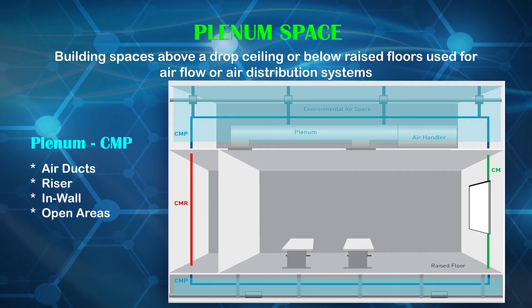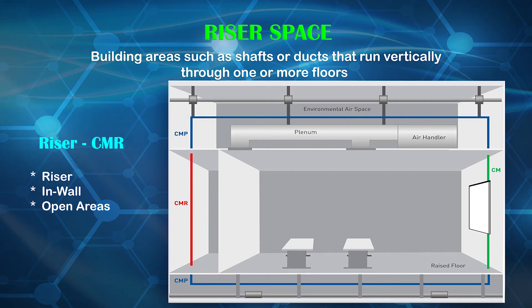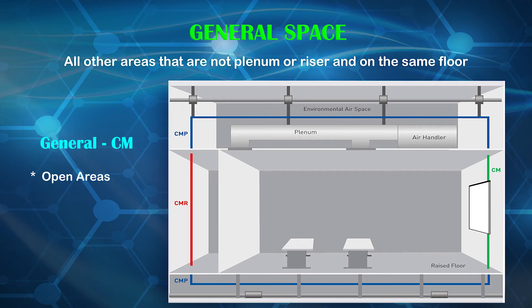Plenum spaces are building spaces above a drop ceiling or below raised floors used for airflow or air distribution systems. They include air ducts, riser in-wall, and open areas. Riser spaces are building areas such as shafts or ducts that run vertically through one or more floors, and include riser in-wall and open areas. General purpose spaces are open areas and all other areas that are not plenum or riser and on the same floor.